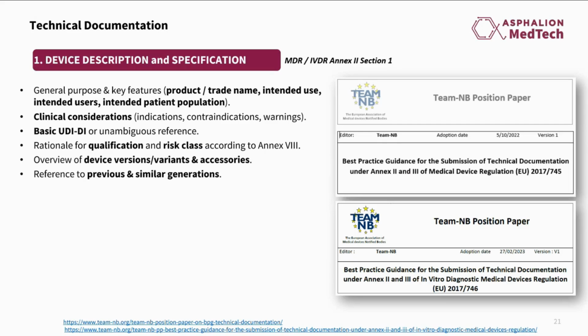Let's briefly review the technical documentation contents. The technical documentation does not have a fixed structure, but we can find in Annex 2 of the medical device regulations the typical contents that it needs to contain, okay? Before starting to draft the technical documentation, it's really important to assess with the notified body whether they have a specific template for submitting the documentation, because in some cases they do have a fixed structure. But if not, you can stick to the Annex 2 points, okay?